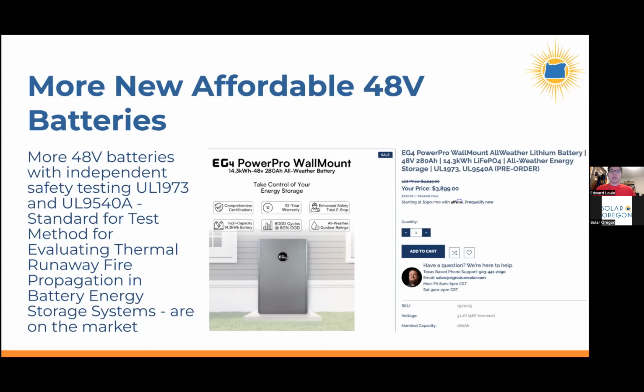That's really good. In the 48 volt battery space, it's a wild, wild west — a lot of batteries being produced by different manufacturers, giving infinite choice, which is good and drives down the price. But not all those batteries have undergone the UL safety testing that's pretty important for getting a system a building inspector will actually sign off on.